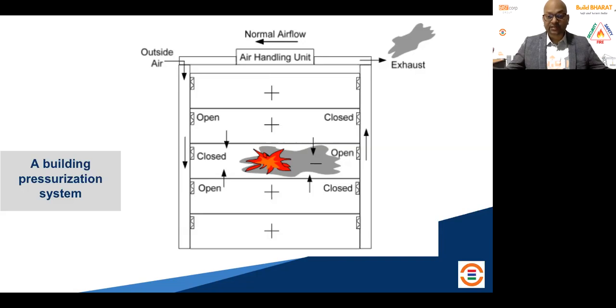You already have firewalls there, but on top of that, if you have openings through ducts, smoke is going to pass through. So you need this mechanical or engineered way to manage your smoke. So typically, what you are doing here is creating a positive pressure on this floor, this floor, this floor, and this floor. So the plus you see on the upper floors and lower floors, you are creating a positive pressure. Here you are going to create a negative pressure. And how are you going to create negative pressure? By opening the exhaust out.